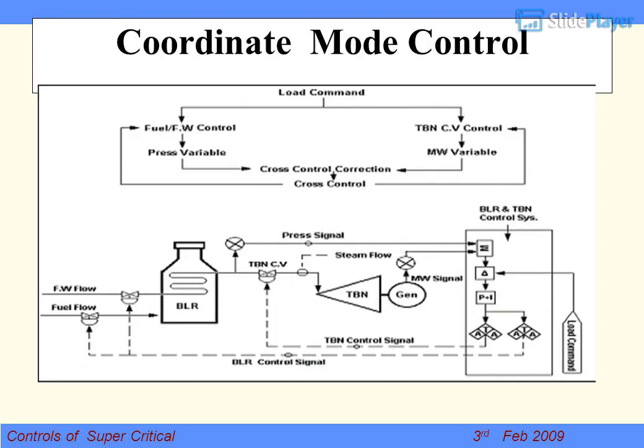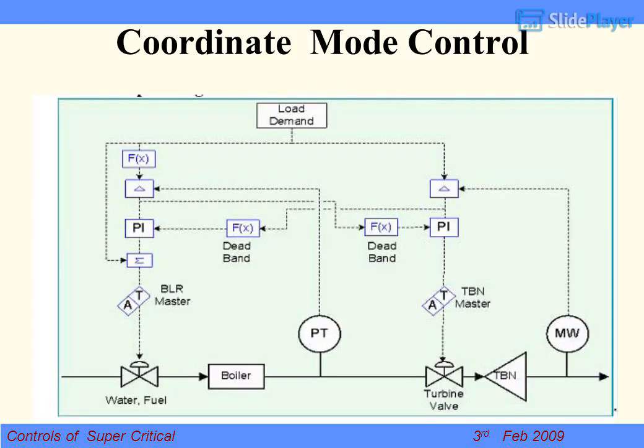Coordinate Mode Control: whenever load is increased, the command is given to increase fuel flow and feed water flow both, and load is increased at the same time to meet demand. Load following will be fast and throttle pressure will not drop. In supercritical units we follow this mode for fast load pickup. This is how CI units generally run. Many logic bits are based on unit capability and auxiliary availability.